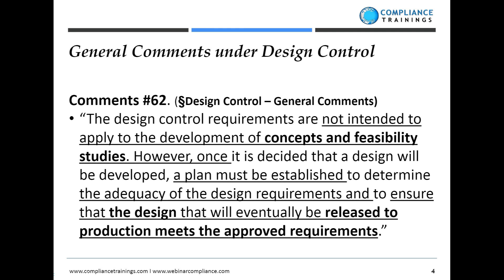One of the reasons design controls were added into the CFR general GMPs: a manufacturer might say they're going to make a wheelchair, but couldn't get all the parts they wanted to design into it, so when they were done they ended up with a trike — and sent it to market with no real justification for the trike. Essentially, the agency says once you've embarked on a device plan, you have to go through the process of developing a plan for how to do it and arriving at the adequacy of design requirements.